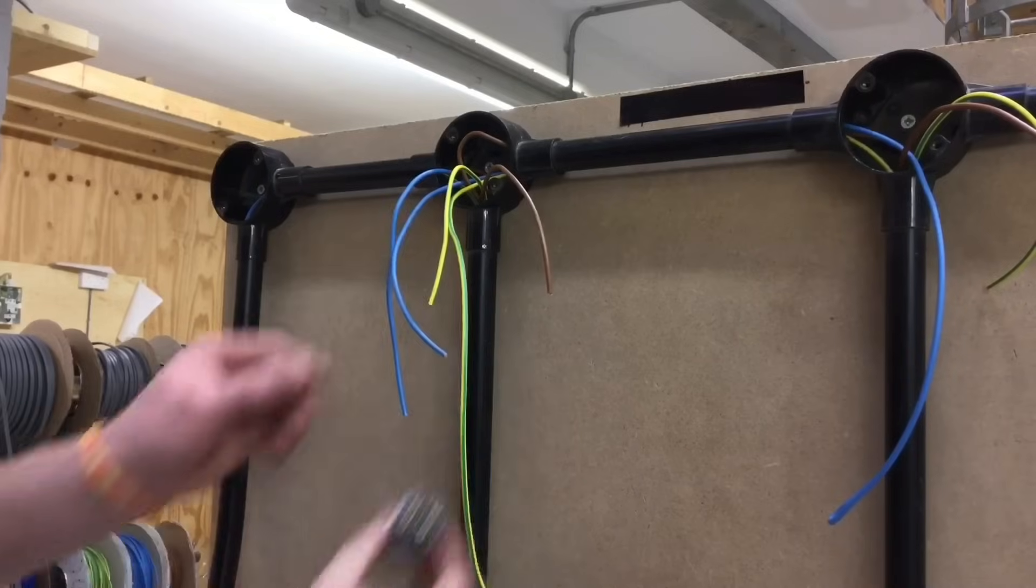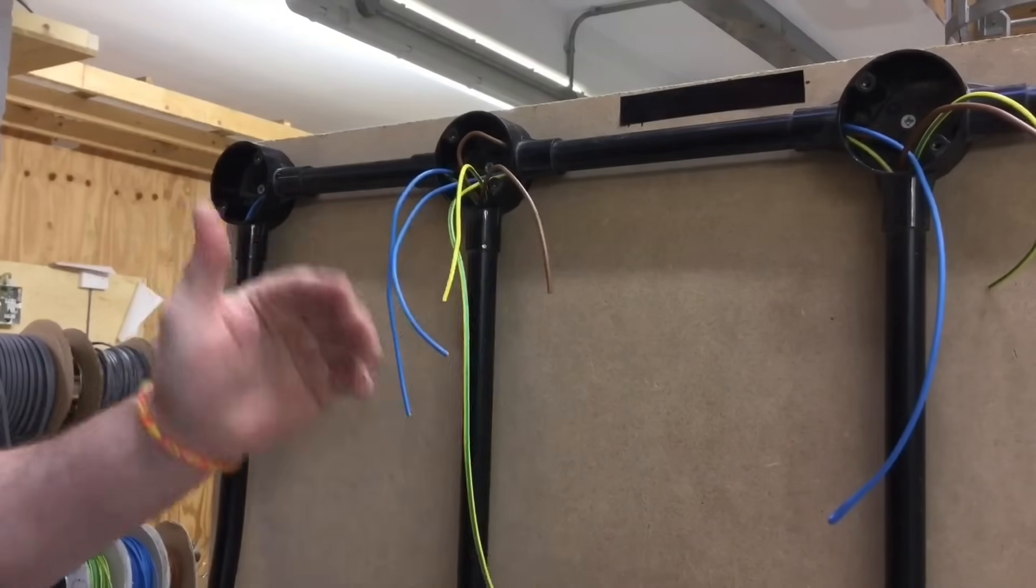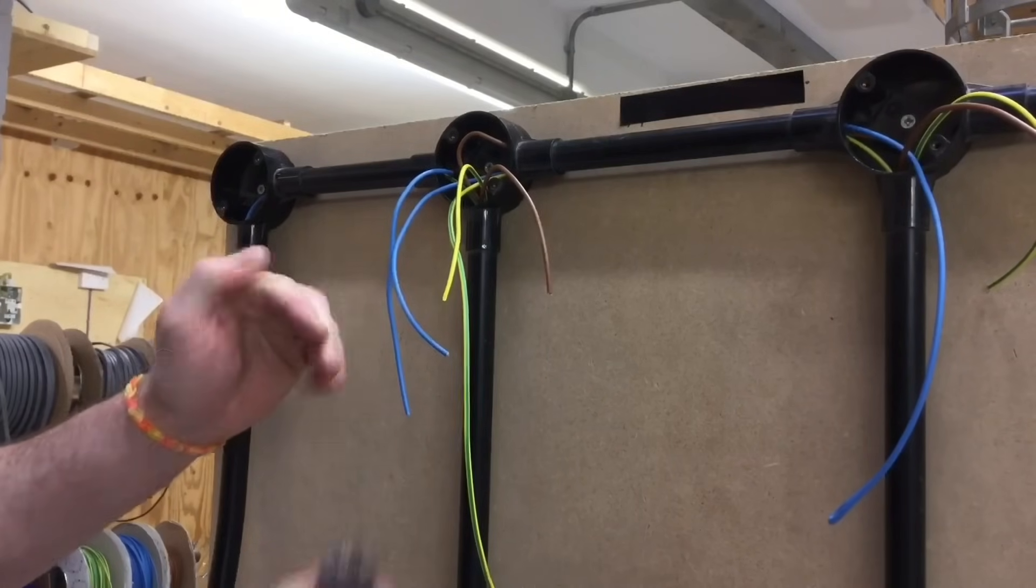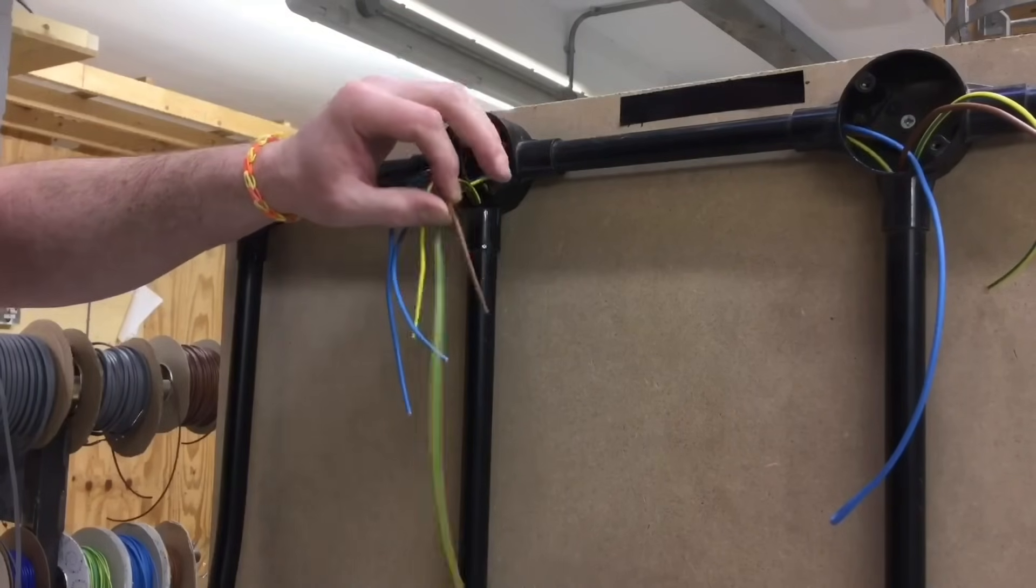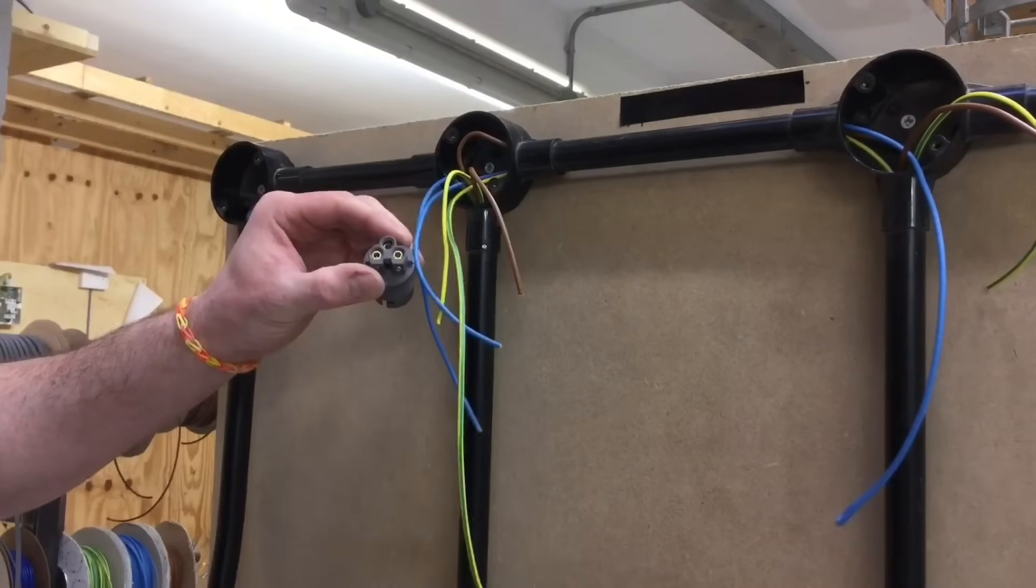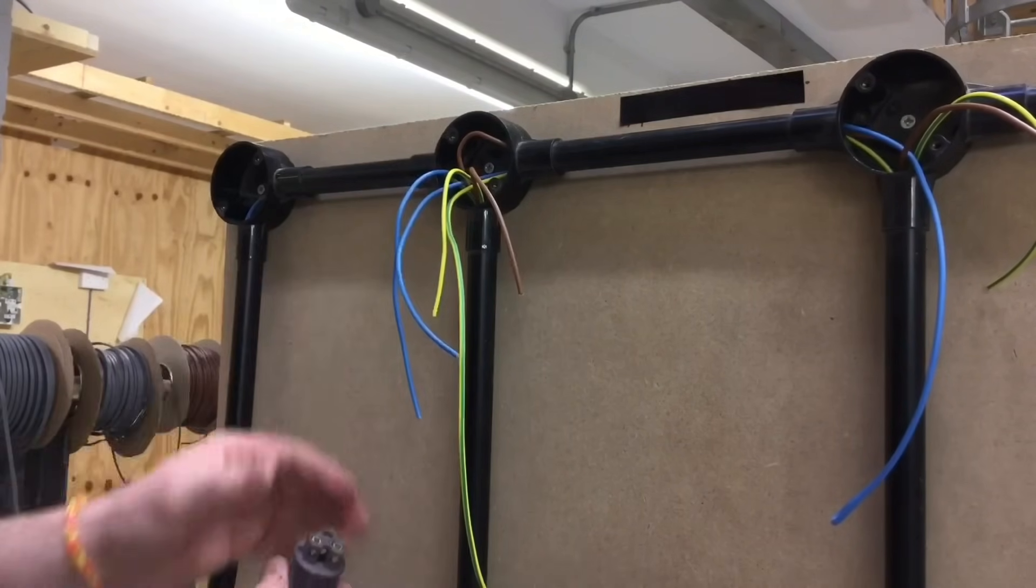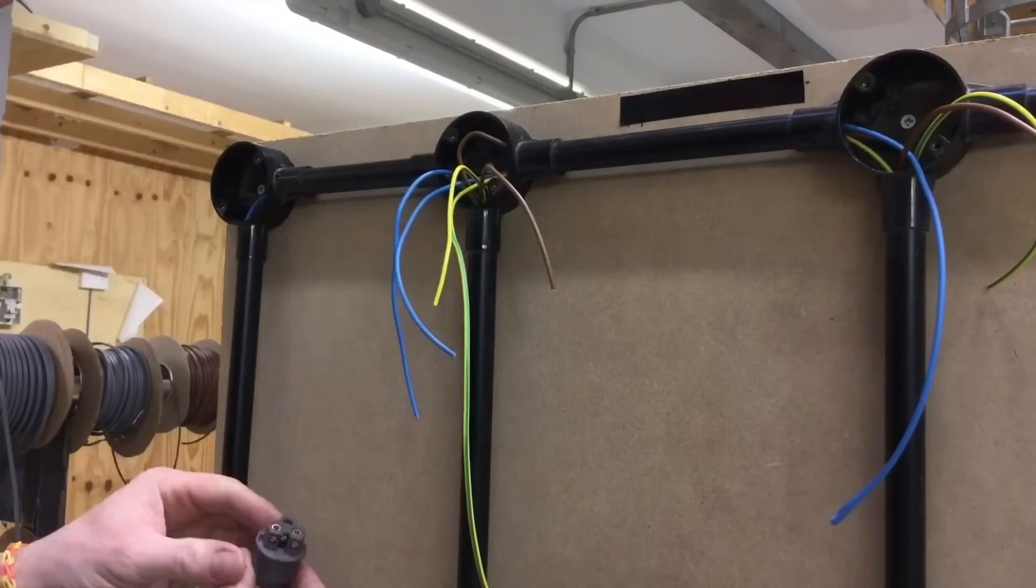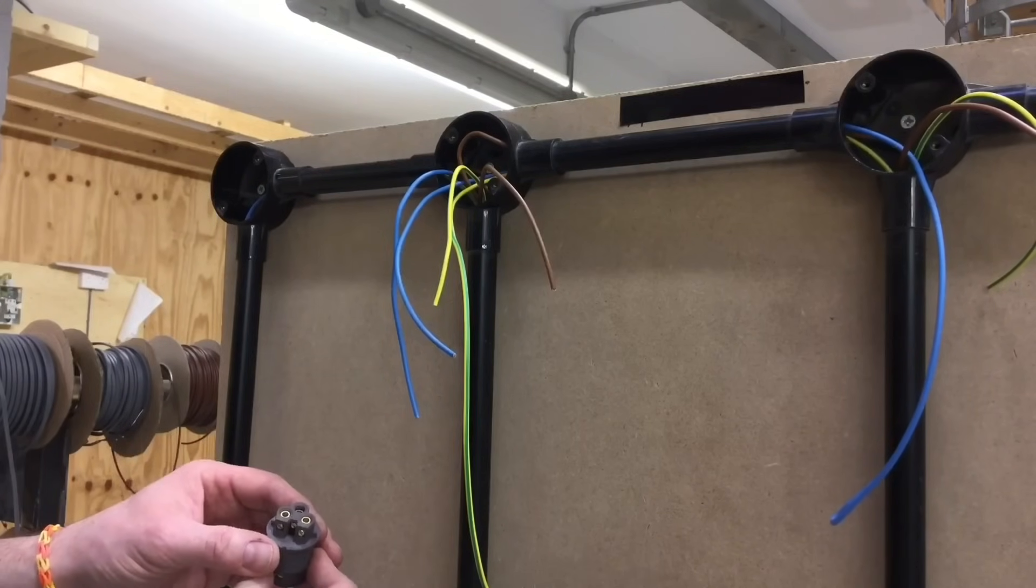Exactly the same as the switch, when we're making the connections in our straight skirted batten lamp holder where there are two cables - so we've got two neutrals and we've got two circuit protective conductors - the insulation will be removed, twisted tight and singled into the actual terminations themselves. Where we've got only the one switching line conductor, we will strip it back, twist it super tight, and double it over for the connections within the actual batten lamp holder itself. Where there's only one it'll be doubled, where there's two they'll be singled using the same method as we used when connecting the actual switch itself.